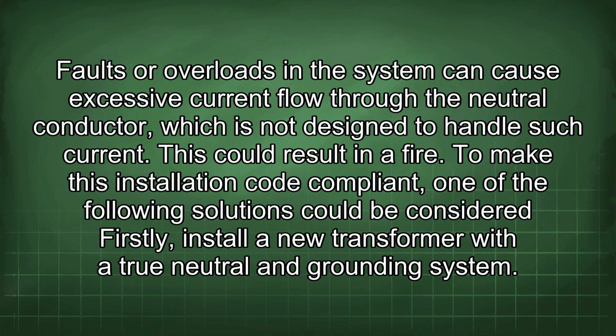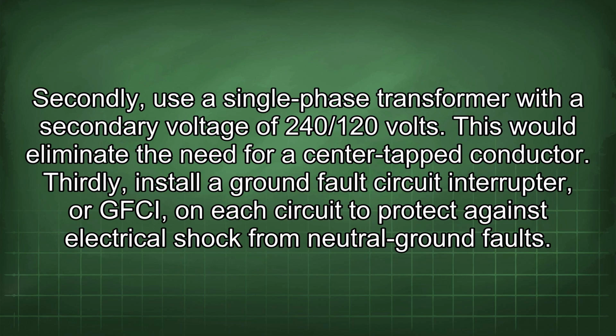To make this installation code compliant, one of the following solutions could be considered. Firstly, install a new transformer with a true neutral and grounding system. Secondly, use a single-phase transformer with a secondary voltage of 240/120 volts. This would eliminate the need for a center-tapped conductor.